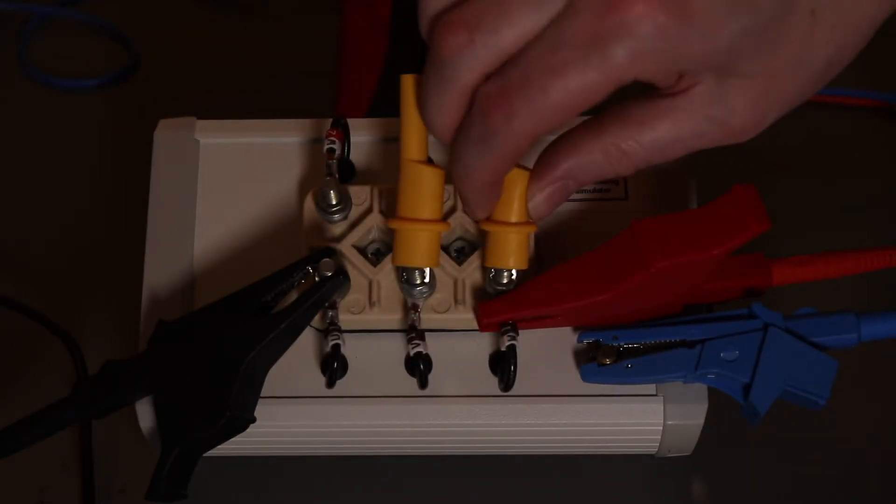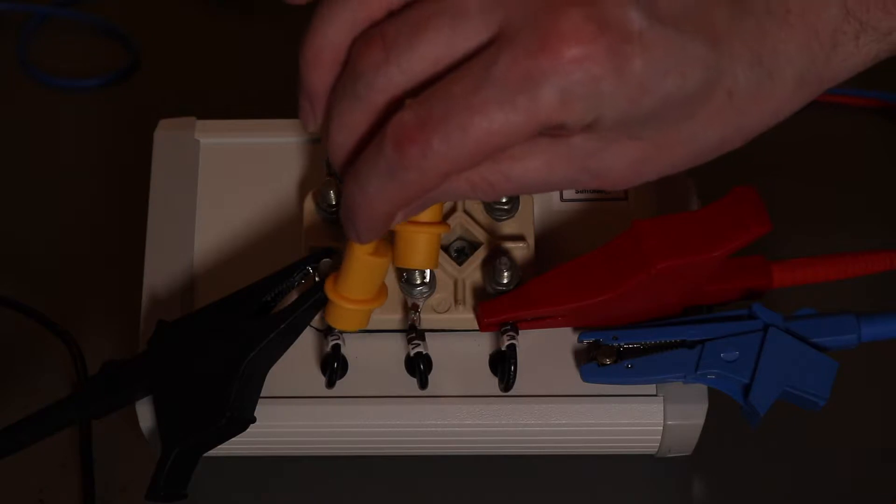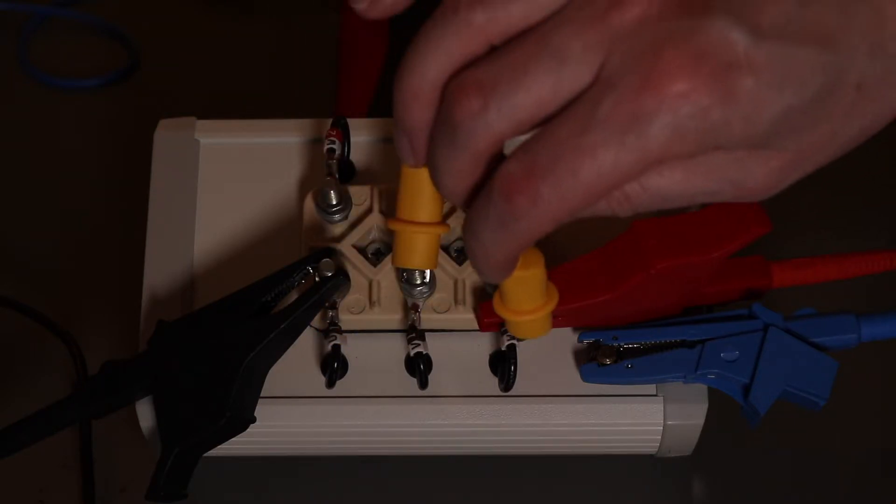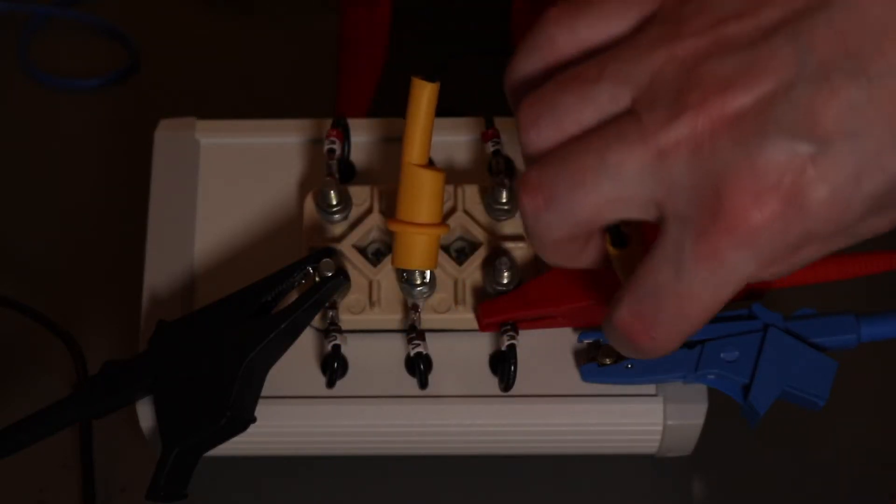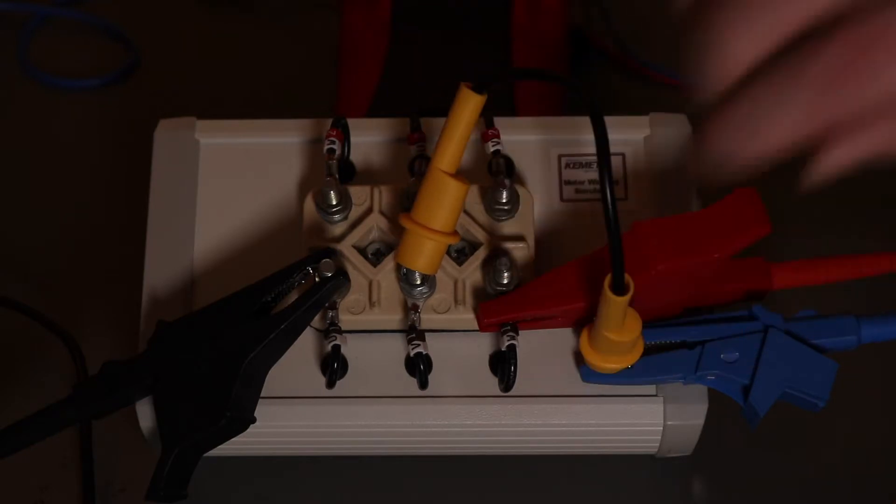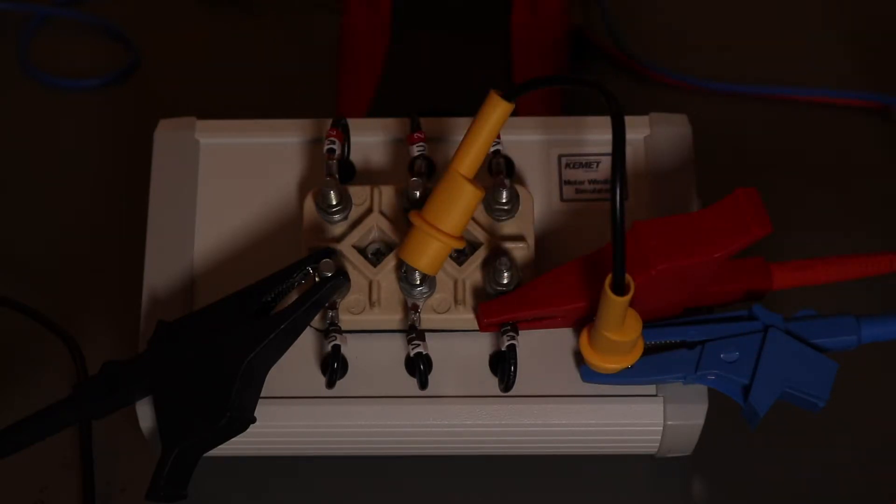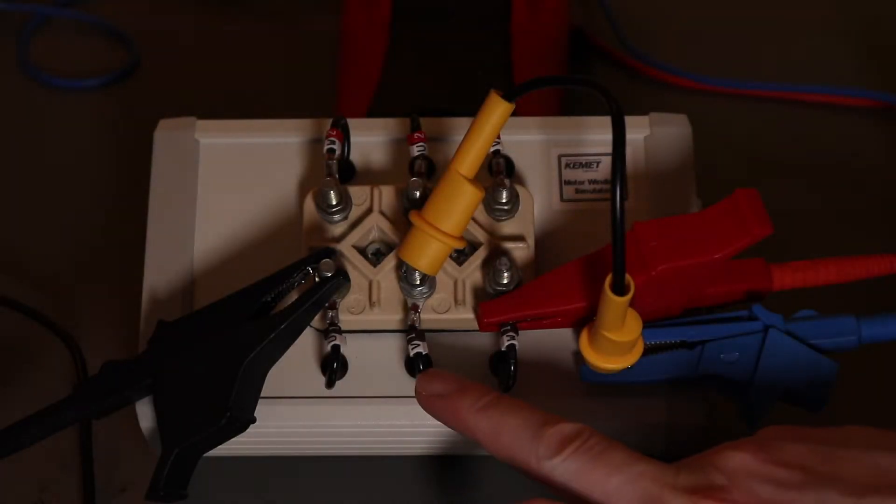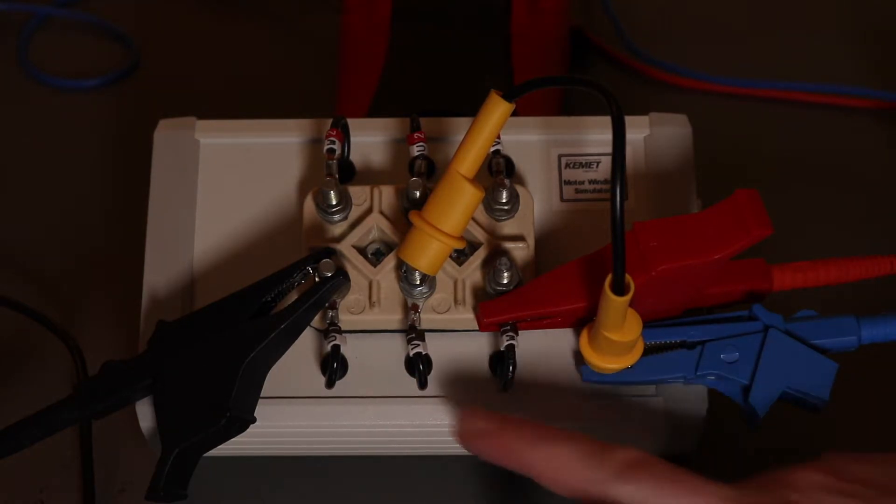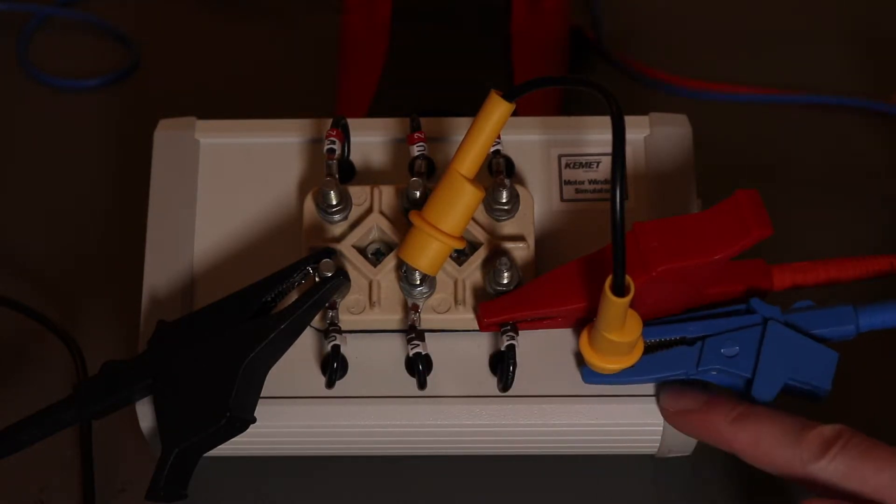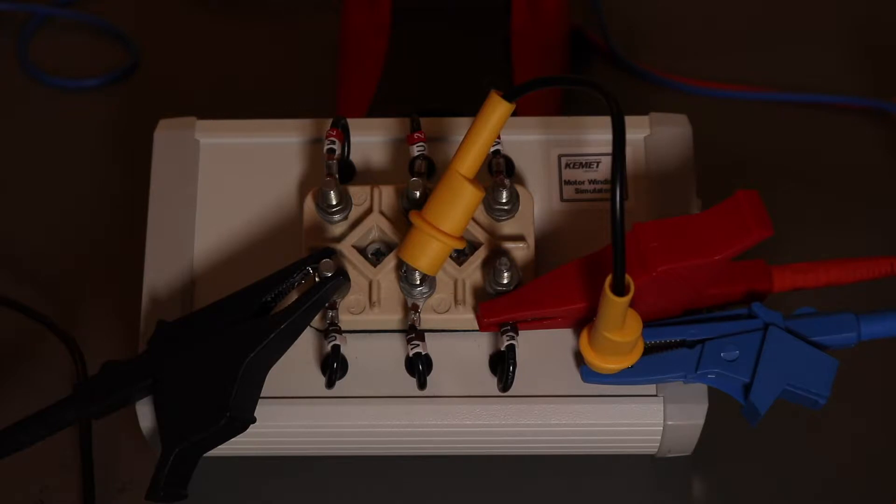I could have the option if I really wanted to test just the leakage from U into W. I could take the V winding and clip that onto earth. Then the leakage from here into here or here into here goes into the guard terminal and is subtracted from the result.